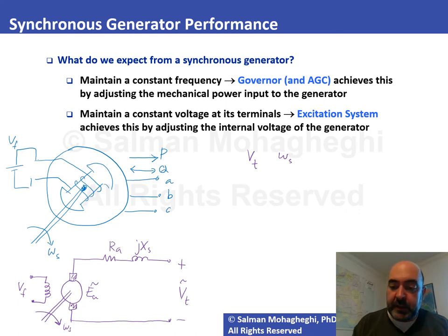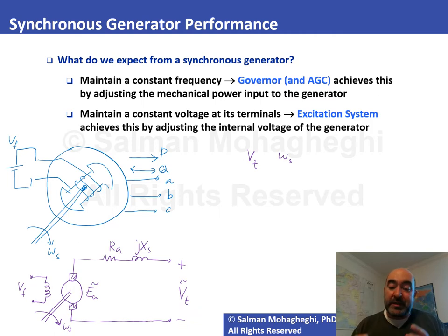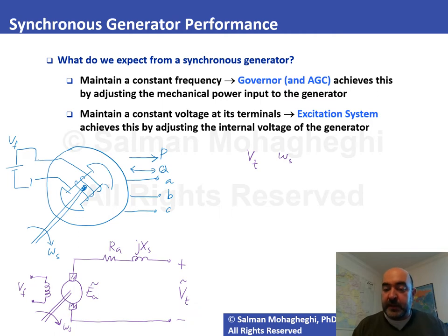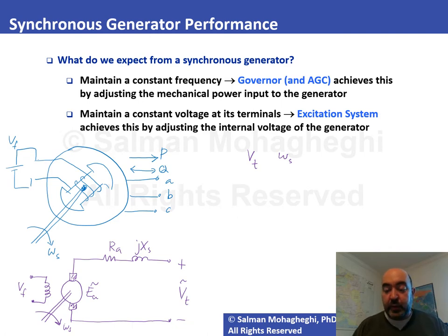The system frequency is directly related to rotor speed. If frequency is low, spinning the rotor faster increases it; if high, slowing it down reduces it. The controller responsible for maintaining rotor speed is the governor system, which monitors output frequency and speeds up or slows down the prime mover accordingly. The excitation system is responsible for controlling the terminal voltage magnitude, adjusting the internal voltage to keep V_T at, for example, one per unit.